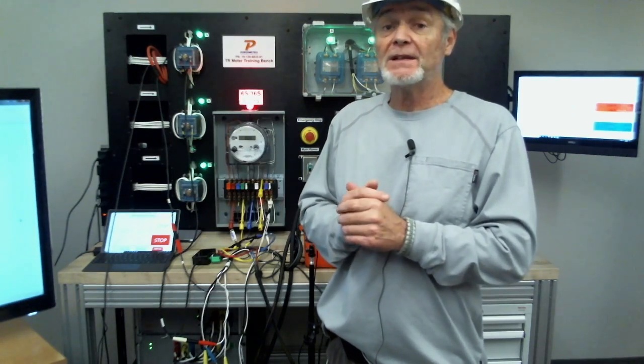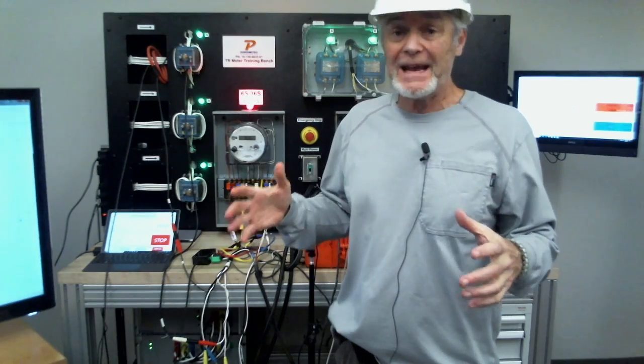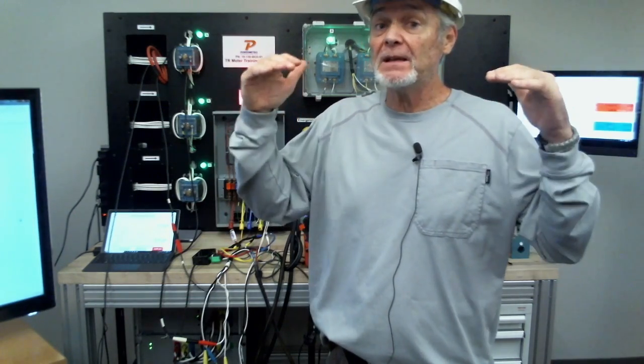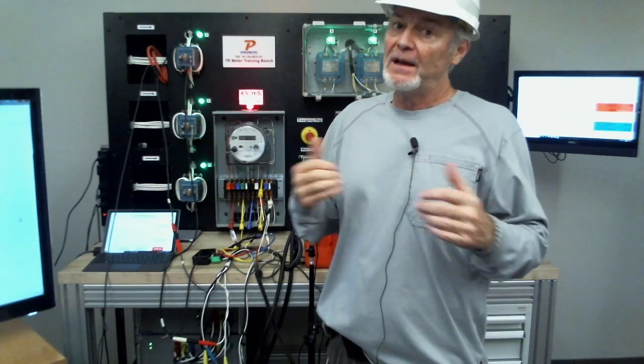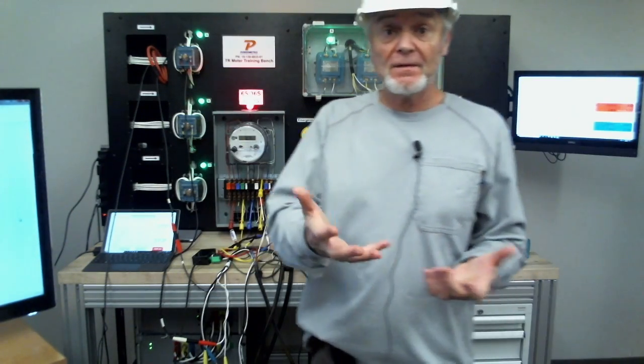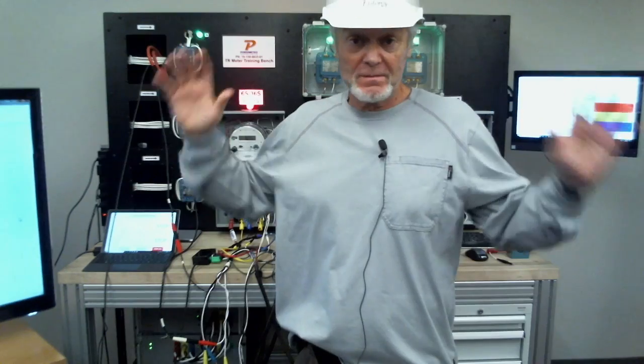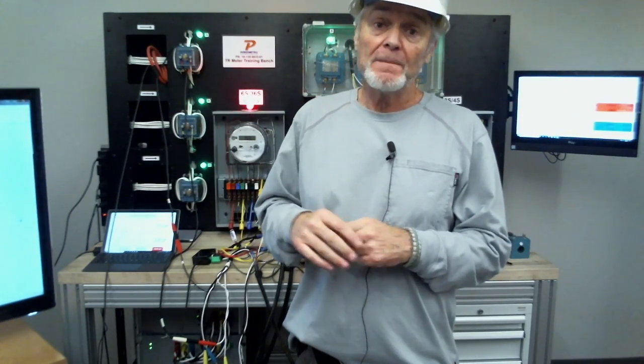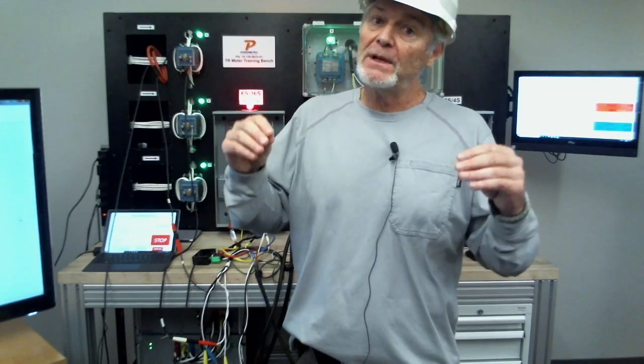If I don't see at least 0.5 secondary amps, I know I'm going to have a tough time testing it, and it doesn't meet the legitimate ANSI test. So if I don't have at least a half an amp there, I know I'm going to have trouble. Sometimes, as you've seen in the videos, we've said thank you, Lord, and just grabbed our stuff and gone on when we've got it with 0.2 or 0.3. But you can't count on that, and again, it's not really a legit test.